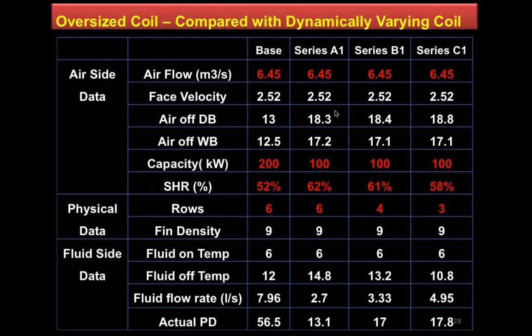So what I would like to highlight here is the condition that we have in the outside environment. We looked at typical conditions of what the space might be, and the leaving coil condition that we want to design for. A typical chilled water supply temperature of 6 degrees Celsius was adopted in this particular study. And here I have a table. First, I will discuss in the form of this table where an oversized coil is compared with a dynamically varying coil. So the base case is my oversized coil. The red numbers are the critical ones that I want you to direct your attention to.